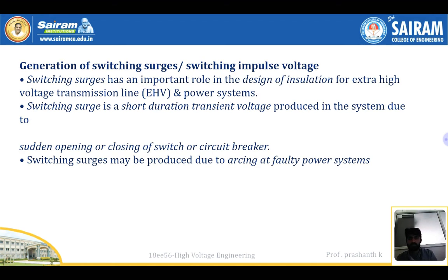Generation of switching surges, switching impulses. Switching surges have an important role in the design of insulation for extra high voltage transmission, like EHV power systems. A switching surge is a short duration transient voltage produced in the system due to sudden opening or closing of a switch or circuit breaker. See how switching surges occur: a heavy rush of electrons occurs while switching, I mean when switching on and off.